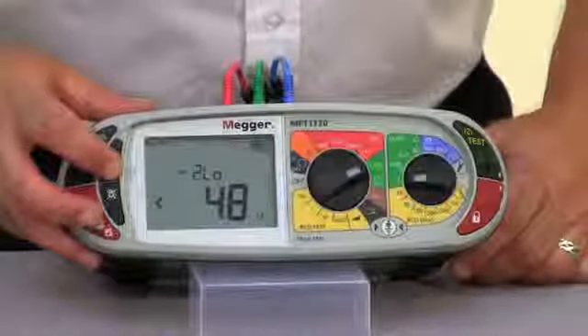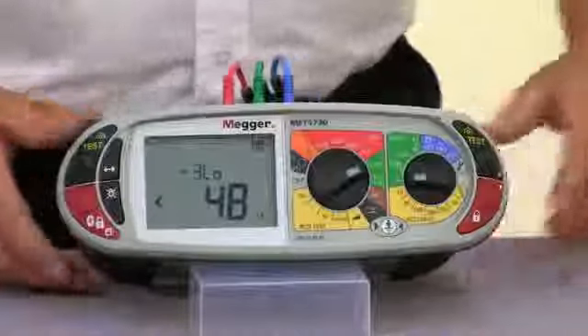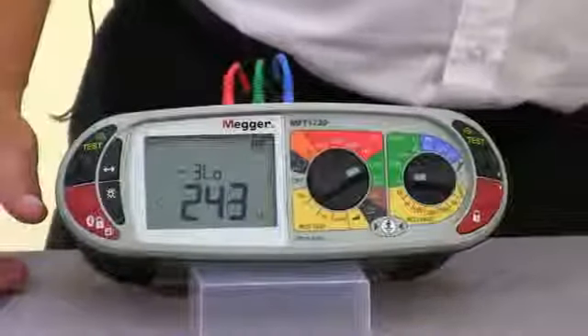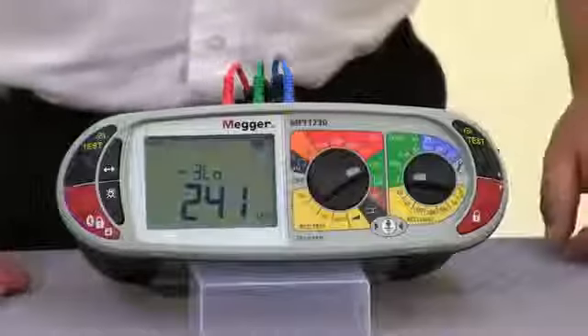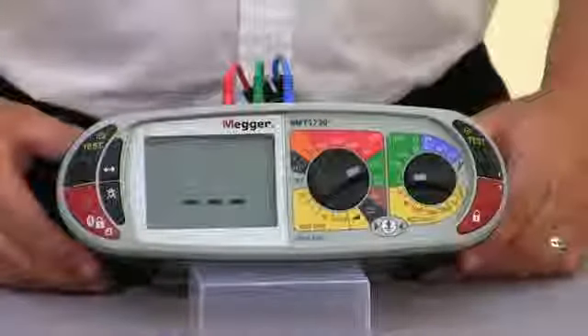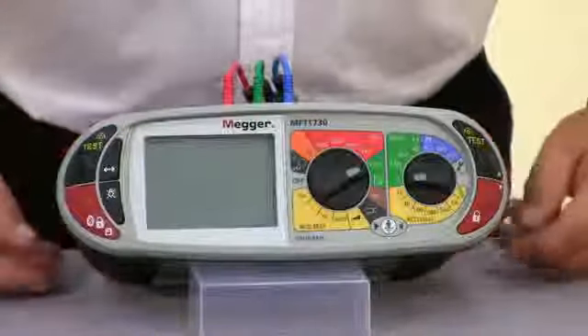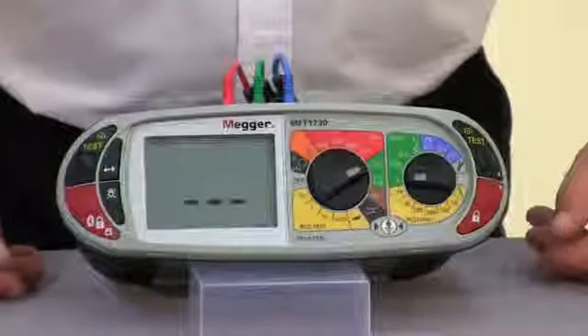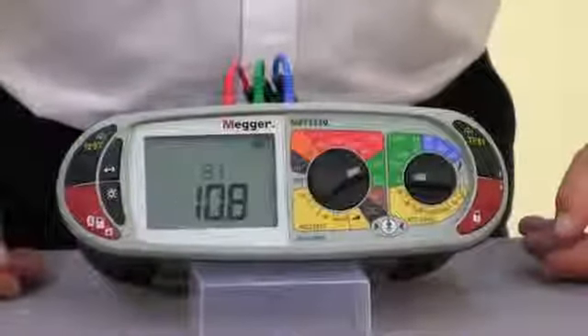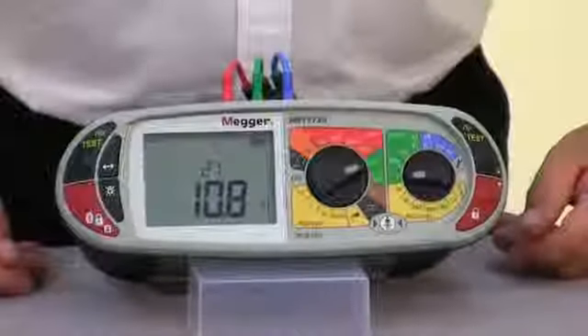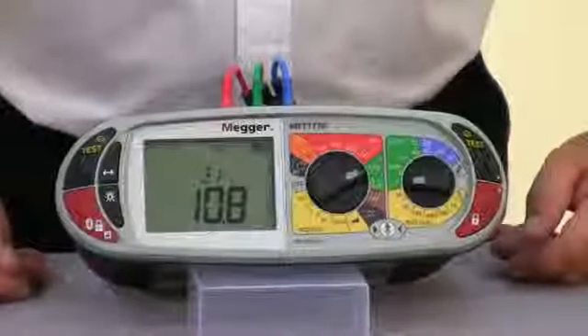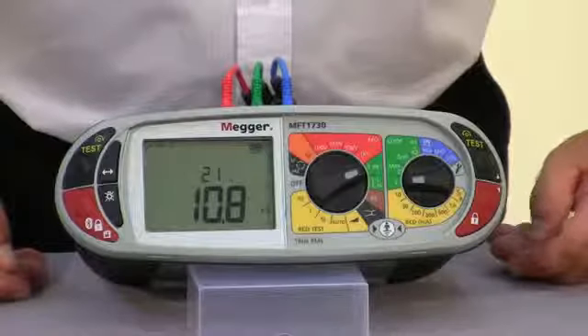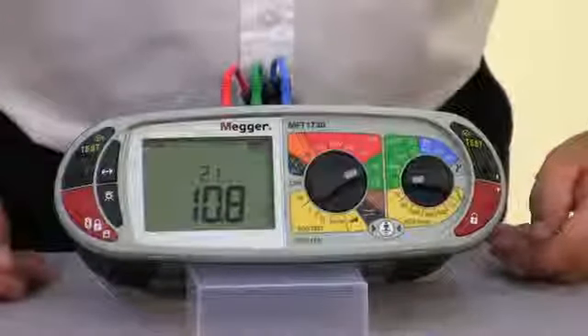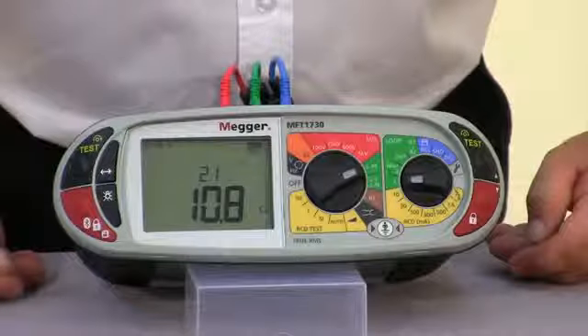So going back to do a standard 3-wire test, so live, neutral and earth connections, applying it to the mains voltage, you get an audible indication from the unit which confirms that it's seen the voltage and has started the test. Now you'll notice that I haven't actually nulled out any of the leads. It's not a requirement with the Megger MFT1700 series when you're doing a loop test to carry out any lead null. So the reading we've got here is 10.8 ohms, and we have a PFC value of 21 amps.